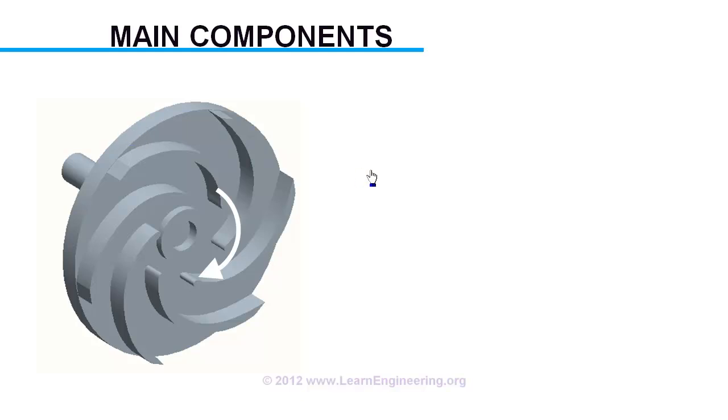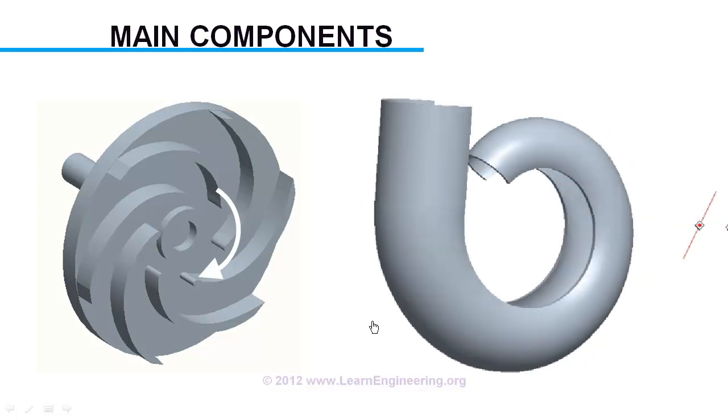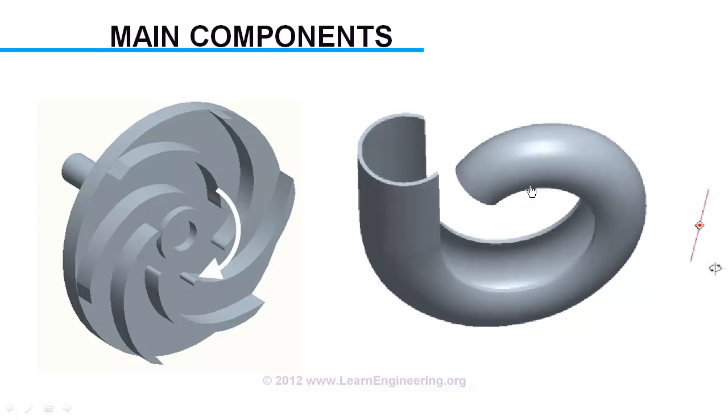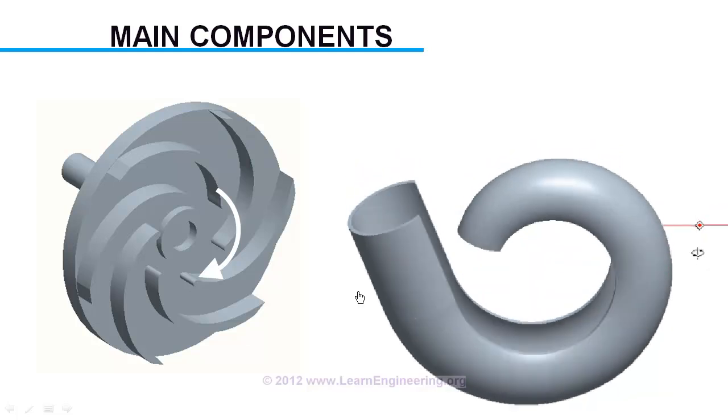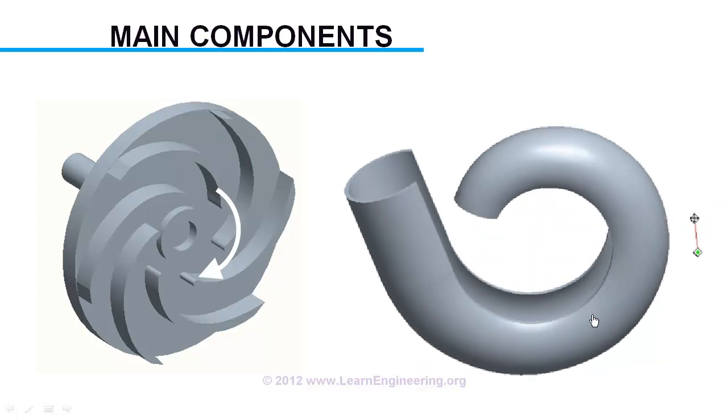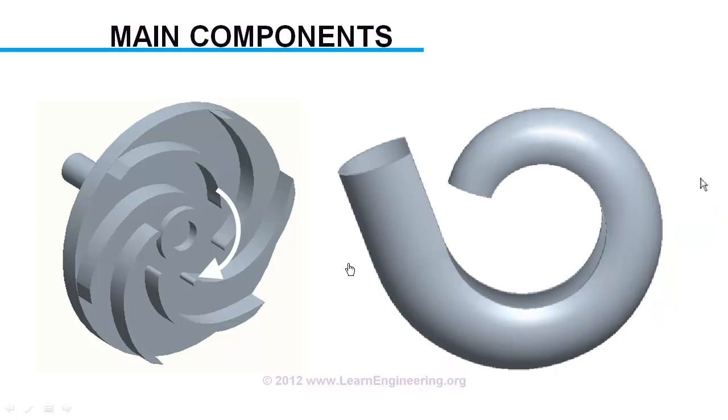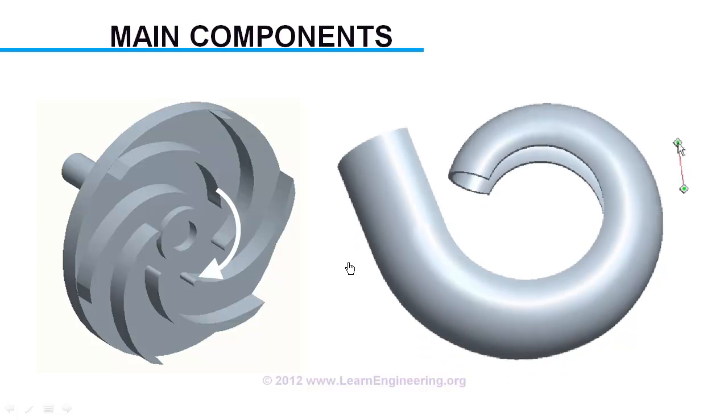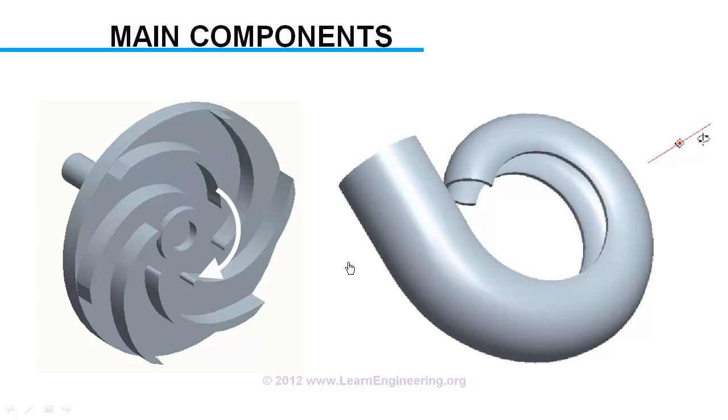Next component is casing, which collects fluid from impeller in an efficient way. The casing has got a special shape, with area of cross-section increases from inlet to outlet. As the impeller ejects fluid throughout casing, along length of casing mass flow rate increases. But increasing area of casing helps in maintaining almost same velocity. Thus volute-shaped casing helps in converting dynamic part of fluid energy to static part.